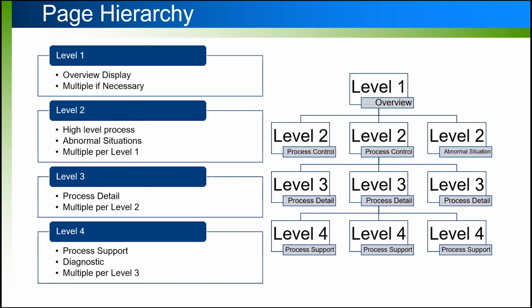This is where you'll get more diagnostic level information. An operator might just be concerned about whether a pump is available or not - can I turn it on or not? Maintenance personnel want to know why. So if you have a VFD that's reported a fault, the operator just cares that there's a VFD fault. Maintenance personnel want to look in and see exactly why that VFD failed, and that's what that level 4 screen is for. You can show multiple values.